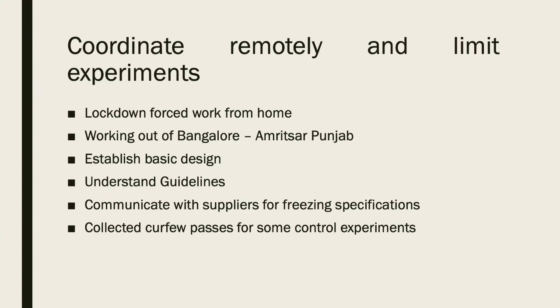Understand the guidelines. This is very important, because generating hydrogen is one thing, as that will ultimately go into some kind of a system where you either burn it or do whatever. But medical oxygen is a different ballgame altogether. As Professor Avasti also brought out, this is something which a human being will ingest. So we had to understand the guidelines described by the Ministry of Health and Family Welfare. They have stringent guidelines describing how a medical oxygen generation system should be, what materials are to be used, and what safety guidelines need to be taken. So all these guidelines were understood.